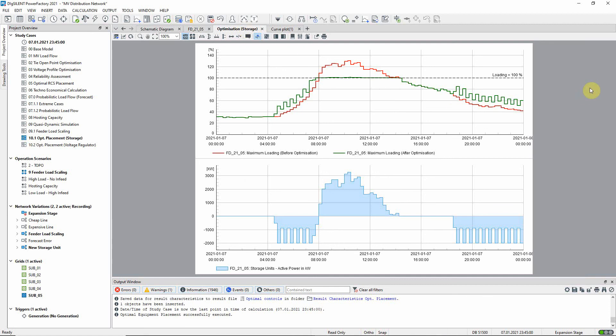In the upper plot the red curve shows the results before the optimization where the feeder is overloaded as we saw before. The green curve shows how the feeder loading has been managed through the introduction of the storage equipment.